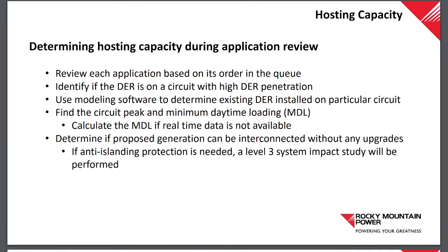Now, maybe from a higher level too, anti-islanding is just, once you get enough generation on a circuit, there's a potential that the generation on the circuit could support it if we disconnect. And we don't want that. We don't want a bunch of aggregated generators controlling voltage, controlling how the grid is operating without us being connected to it, because then we lose control. So when we talk about it, we don't want that to happen. That's anti-islanding. What's the protection to ensure that does not happen? Okay.